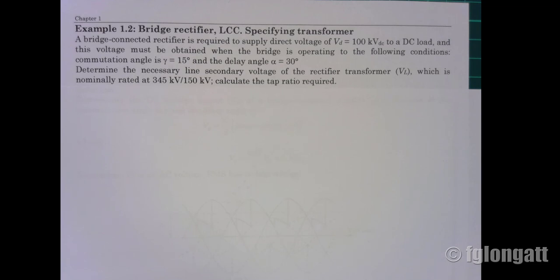This is the technology used for HVDC links using thyristors, and what we want to do here is specify the transformer. There is a short statement here: a bridge-connected rectifier is required to supply a voltage of 100 kV DC to a DC load.